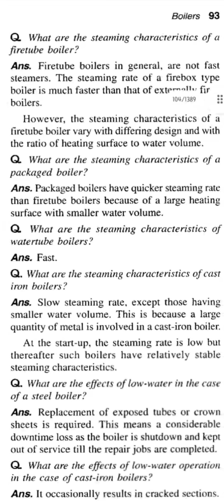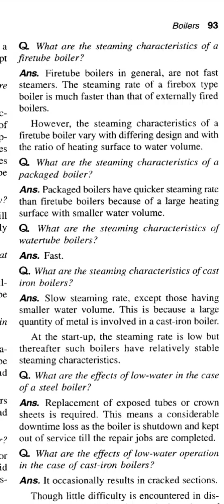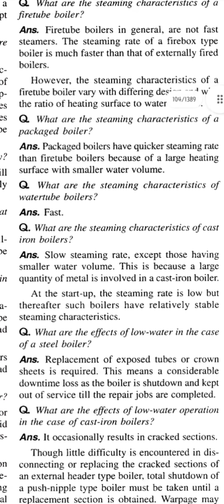Question: what are the steaming characteristics of a fire tube boiler? Fire tube boilers are generally not fast steamers. The steaming rate of a firebox type boiler is much faster than that of externally fired boilers. However, the steaming characteristics of a fire tube boiler vary with differing design and with the ratio of heating surface to water volume.